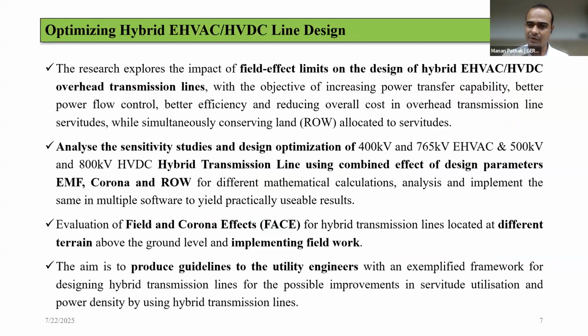For the safer side, we have taken a case study for 400 kV HVAC and 500 kV HVDC, because both are very similar in terms of magnitude, and the overall right of way considerations and electromagnetic field concerns are very close to each other. That would be the initial stage, and subsequently we raised the voltage to 765 kV and 800 kV HVDC.